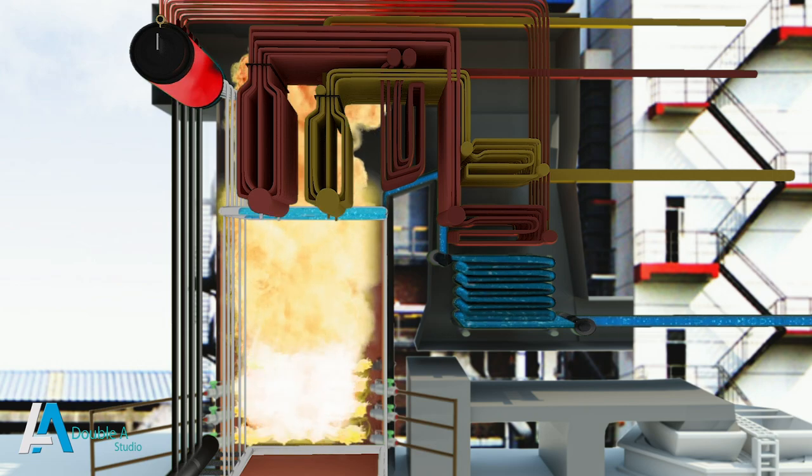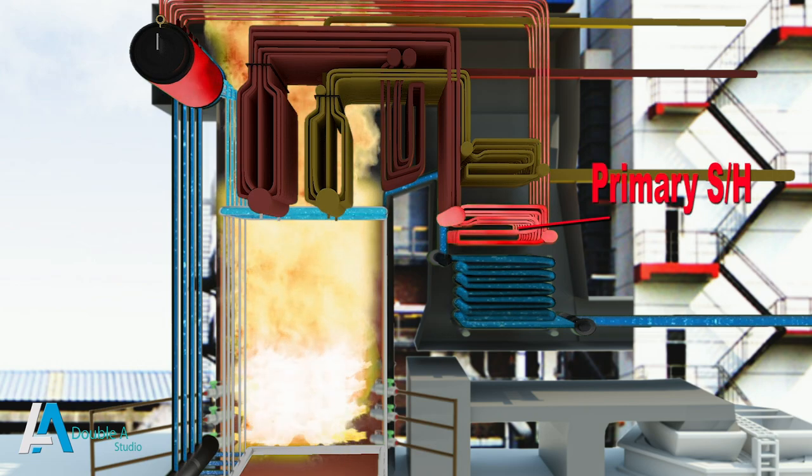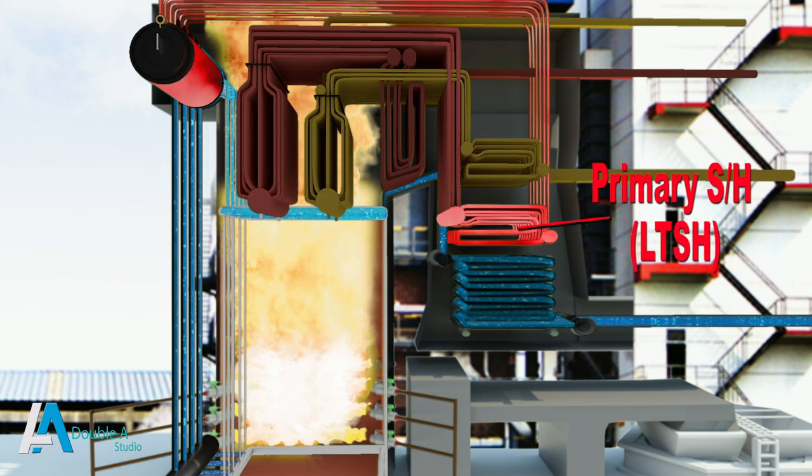Saturated steam coming out of the boiler drum first goes to the primary superheater located in the convection zone. This primary superheater is also called LTSH — that is, Low Temperature Superheater. The heat of the flue gases passing across it is absorbed by the LTSH, which in turn increases the temperature of steam inside the tubes.